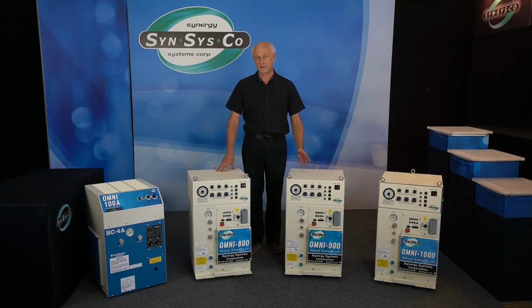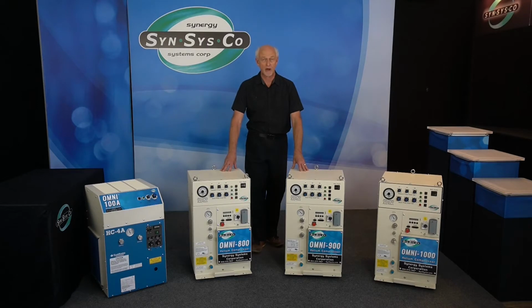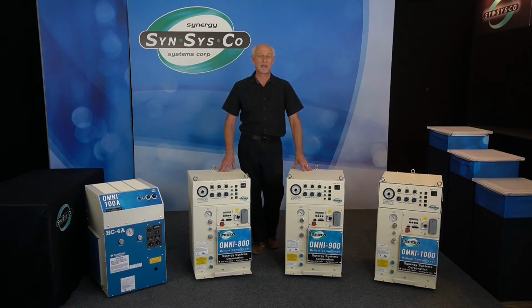Because of this unique capability, an OMNI can be used to replace existing legacy compressors approaching the end of their useful life and no longer economically repairable. To install an OMNI, you simply select the model most appropriate to replace the compressor you have. Once selected, you disconnect your existing compressor, roll in the OMNI, hook up the utilities, hook up the cryopumps using exactly the same cables and connectors, and go right back to business. So it's a fit, form, and function replacement.